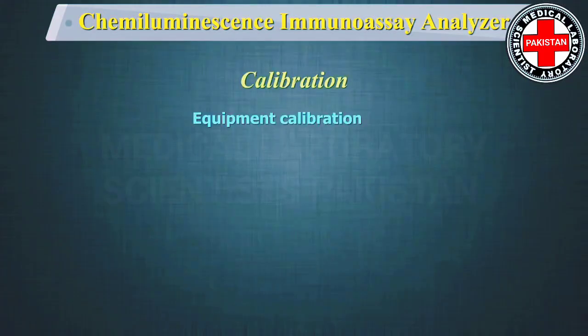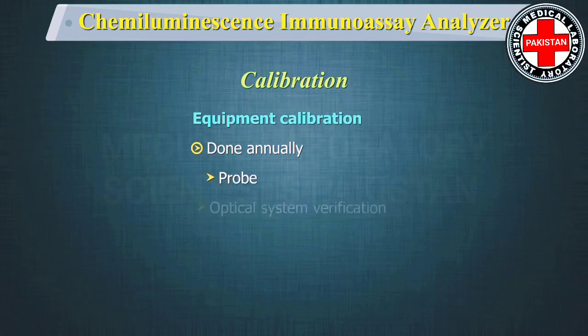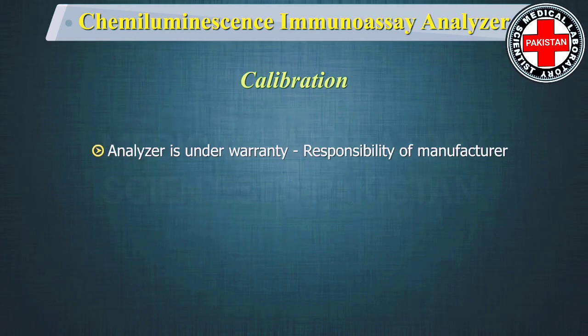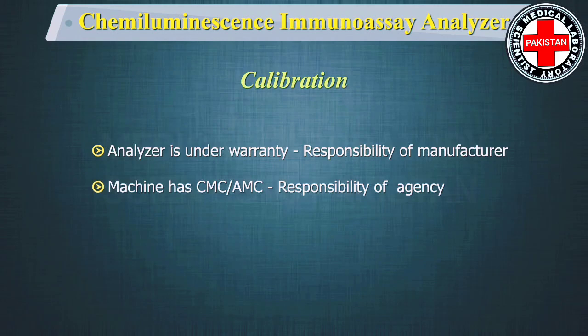Equipment calibration is to be done annually by the technical support team of the manufacturer, covering probe, optical system verification, and wash zone aspiration as per the manufacturer's format. If the analyzer is under warranty, this is the responsibility of the manufacturer. If the machine has a maintenance contract, it is the responsibility of the agency depending on the terms and conditions. Check with your tech support for the calibration schedule and the components to be calibrated.